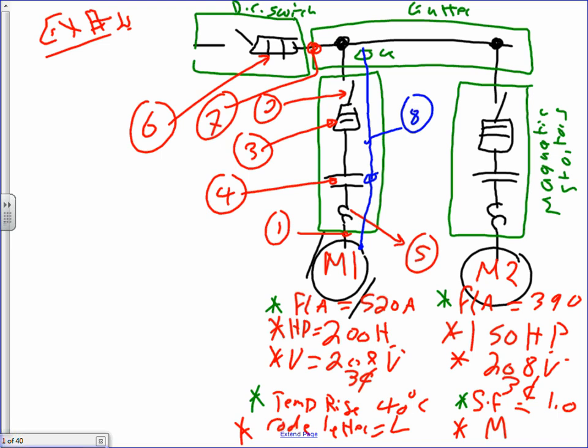You guys remember we did one that was single phase in the fall? Anybody remember that? Doing a single phase one, no? It has been a long time ago. We did the single phase exactly the same, it was single phase. So I thought you can't get out of the industrial project without doing some calculation at least. Number 8 is an equipment grounding conductor. Is there anything you would like me to read? If there's no service factor, Kerry, the service factor will be assumed one.